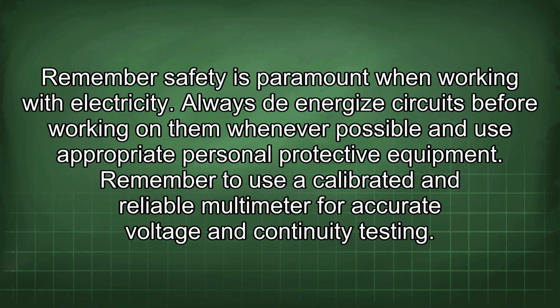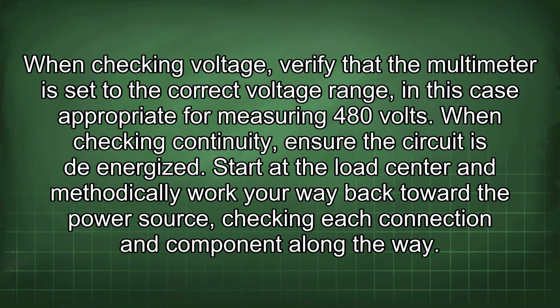Always de-energize circuits before working on them whenever possible, and use appropriate personal protective equipment. Remember to use a calibrated and reliable multimeter for accurate voltage and continuity testing. When checking voltage, verify that the multimeter is set to the correct voltage range, in this case appropriate for measuring 480 volts. When checking continuity, ensure the circuit is de-energized. Start at the load center and methodically work your way back toward the power source, checking each connection and component along the way.